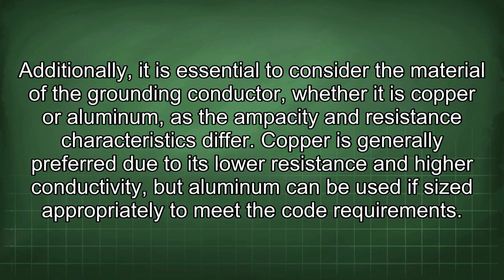Additionally, it is essential to consider the material of the grounding conductor, whether it is copper or aluminum, as the ampacity and resistance characteristics differ. Copper is generally preferred due to its lower resistance and higher conductivity, but aluminum can be used if sized appropriately to meet the code requirements.